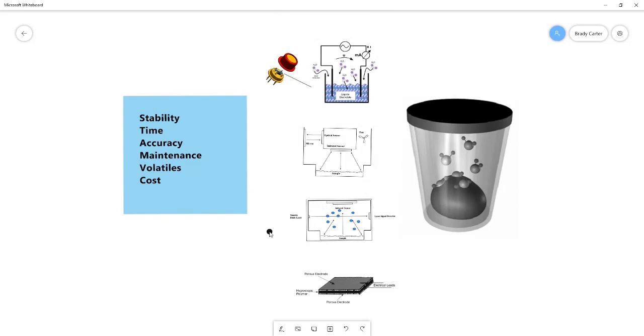And so now if we consider each of our distinguishing factors, when we talk about instrument stability, it's really, will I get the same answer every time? And that's influenced by outside factors like the user that's using it and whether or not he's getting the instrument dirty. In particular, the chilled mirror and even the tunable diode laser depend on cleanliness. The mirror and the infrared sensor can't make the right measurements if they're dirty, and so they are particularly susceptible to those kinds of factors. As well, the tunable diode laser is actually susceptible to pressure changes, so any elevation changes will impact its readings. And in fact, each reading needs to be adjusted based on the pressure.